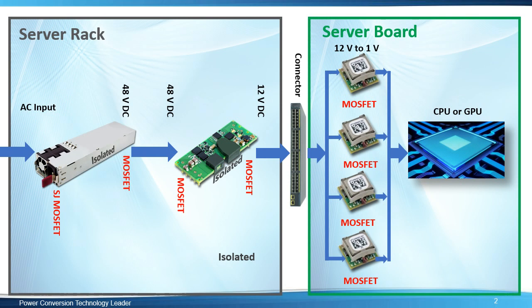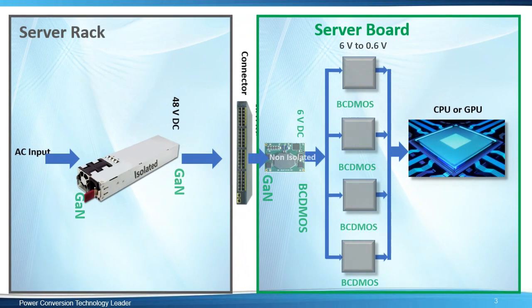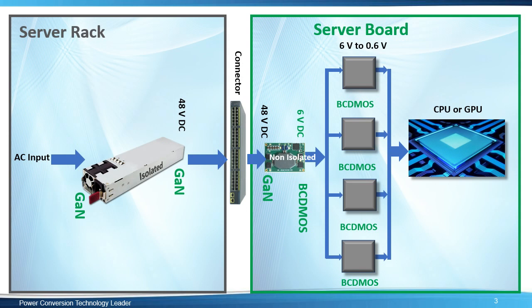Here we see this new topology where the input of the server board is 48 volts. 48-volt input eases the distribution of high power and improves efficiency. The evolution from legacy 12-volt server racks to 48-volt racks reduces energy losses by over 30 percent. Additional key system-level benefits for 48-volt in-rack distribution are copper utilization and distribution losses. For a given power level and bus cross-section, 48-volt systems reduce distribution bus losses by 94 percent compared to 12-volt designs.